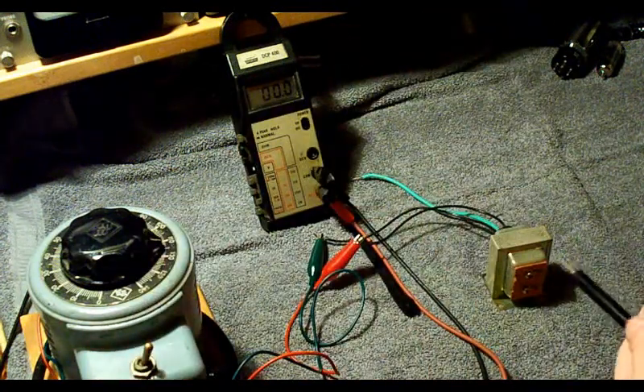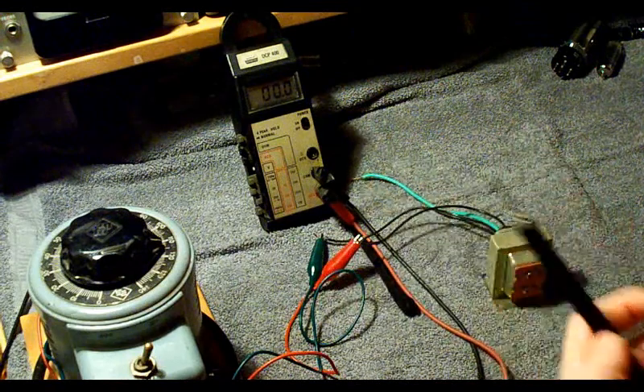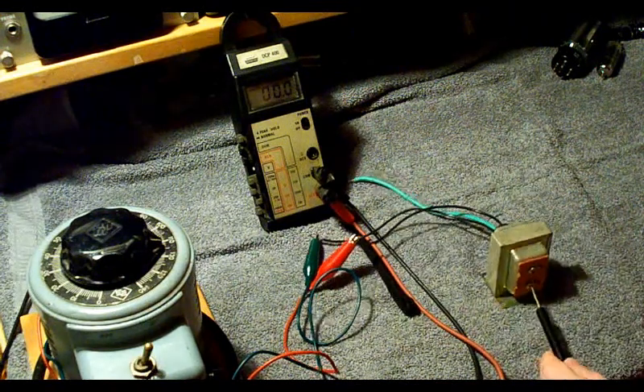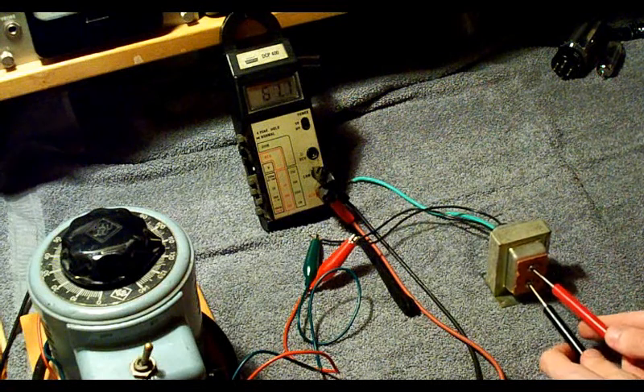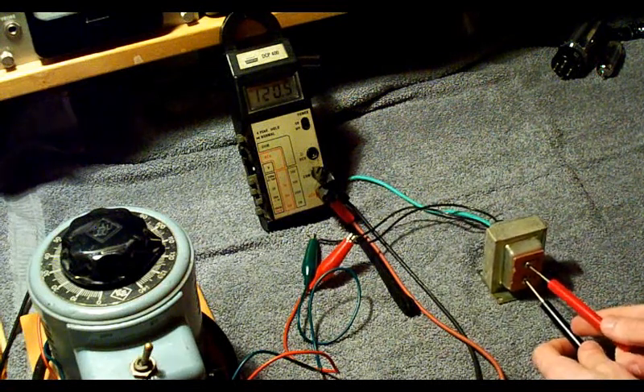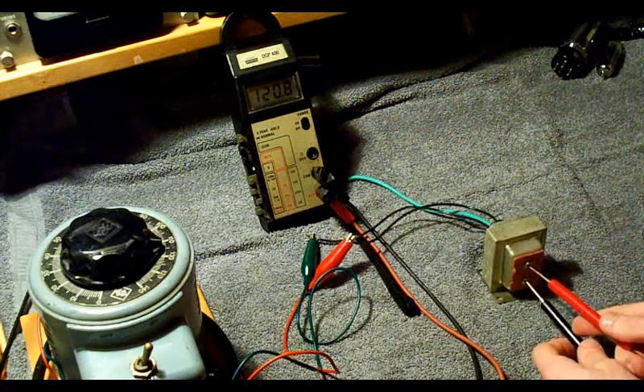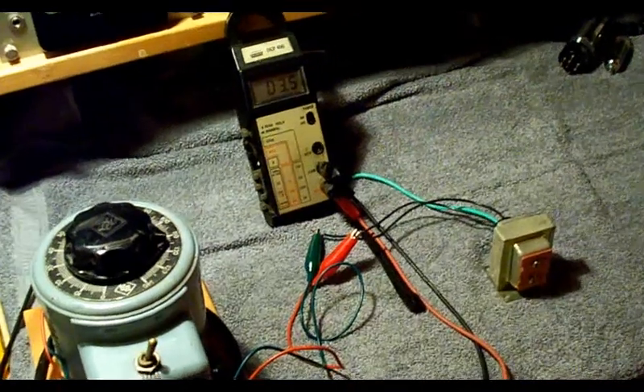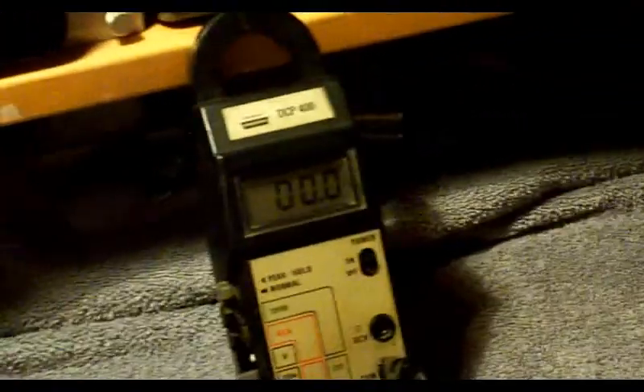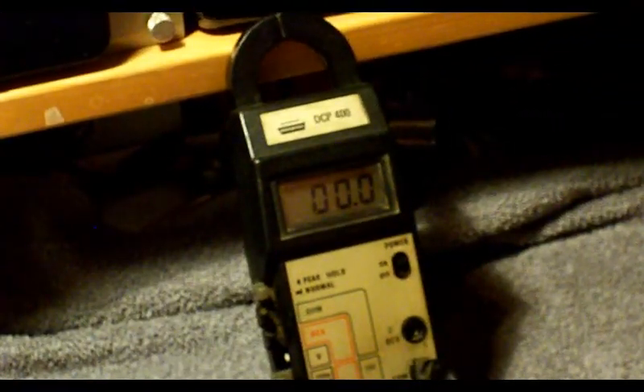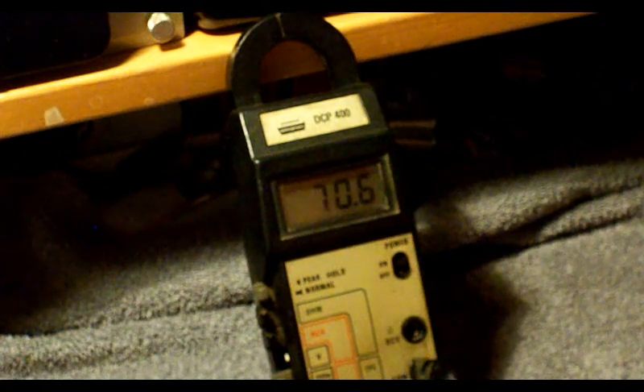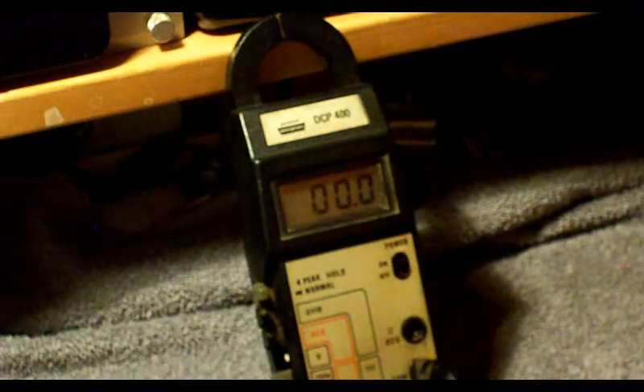Right now, this transformer is energized and it didn't trip a breaker. You wouldn't think anything is wrong until we read the output voltage. And look at that, 120 volts. Can you see that? We have 120 volts coming out of the output of this transformer. Isn't that something? Let's get right in on that meter. Now I'm connecting right across the secondary. 120 volts. De-energize.